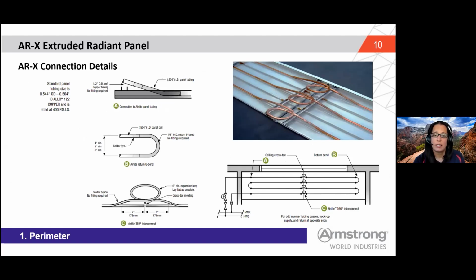So actually connecting the panels together for the hot and cold water. This shows down here if you have the ceiling cross T. If you have two panels together, we send a lifting tool with these perimeter panels. You lift it up and field solder these interconnects in between the two panels. And at the ends, so say at the end of a 16-foot length, again, it is cut in the field to length to fit between the walls or columns or whatever.